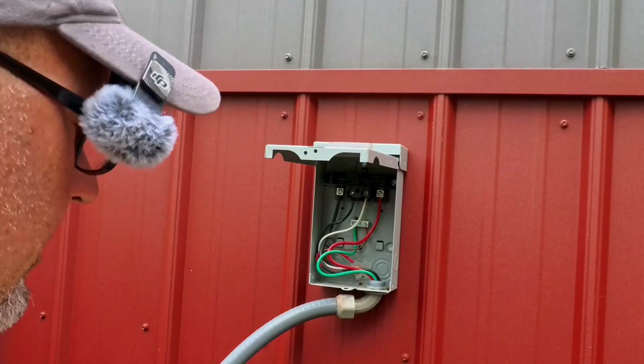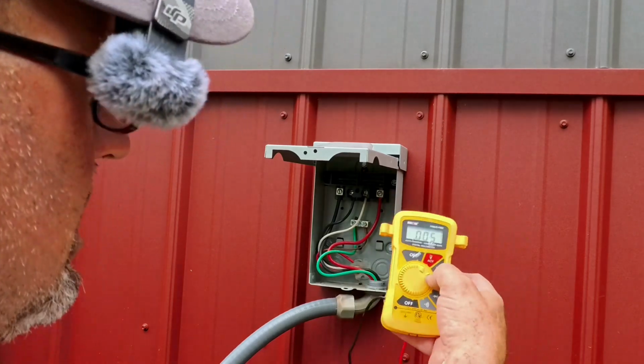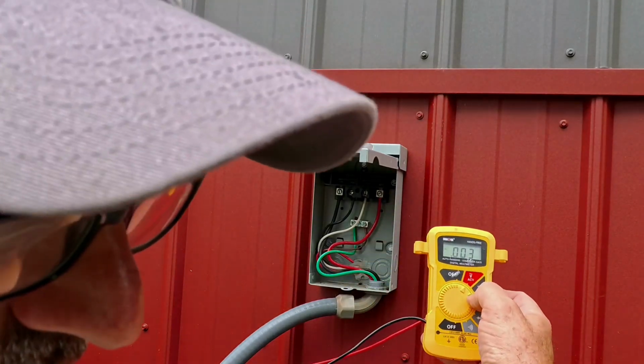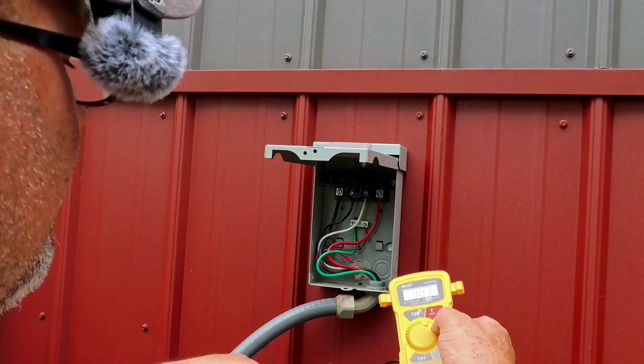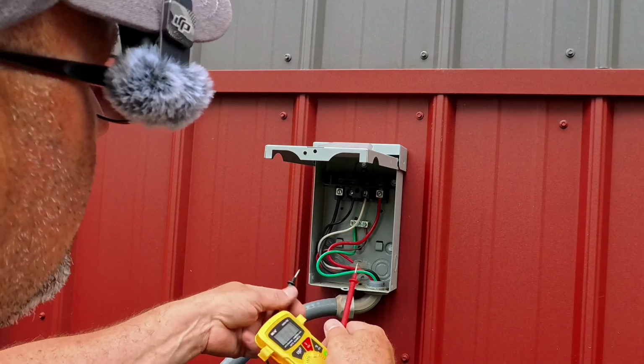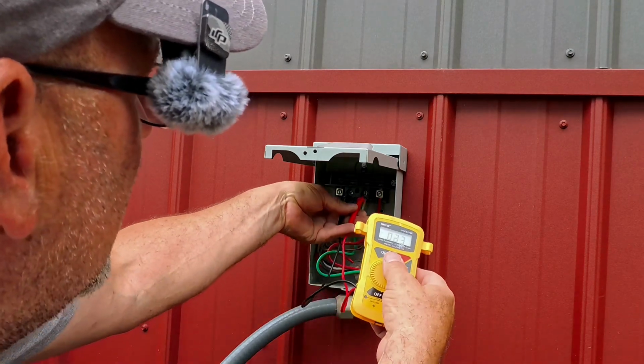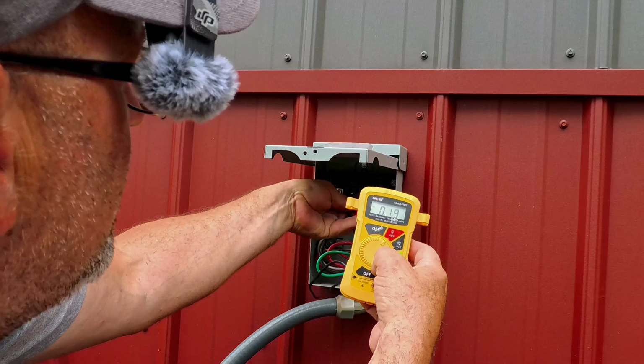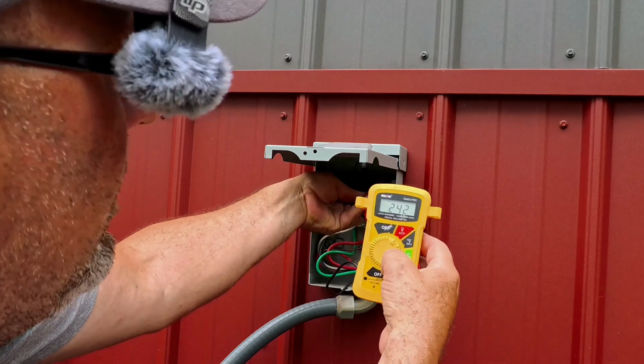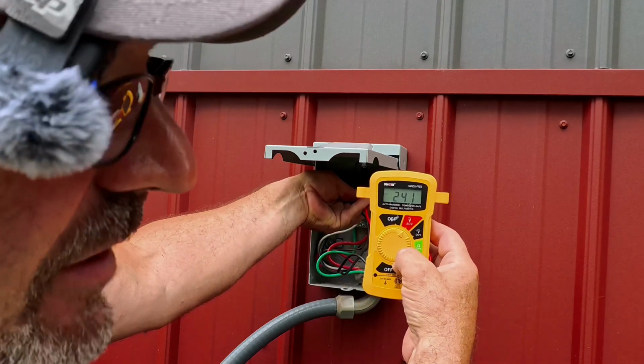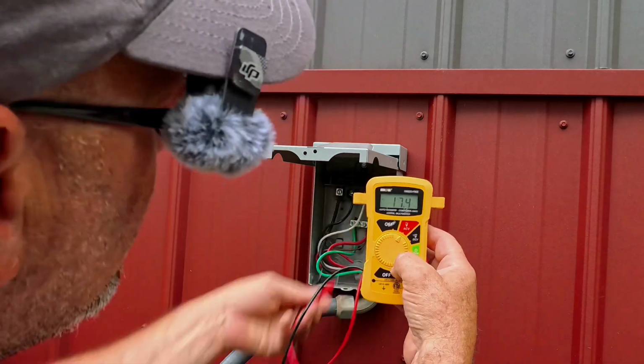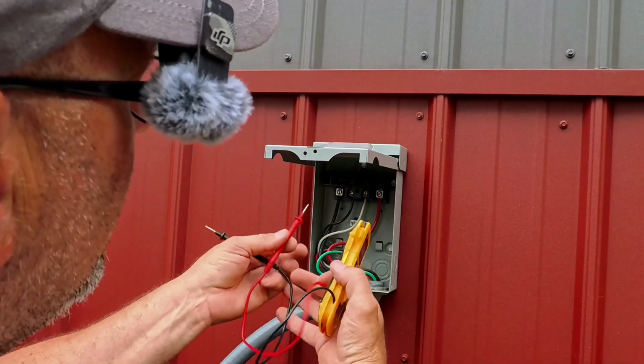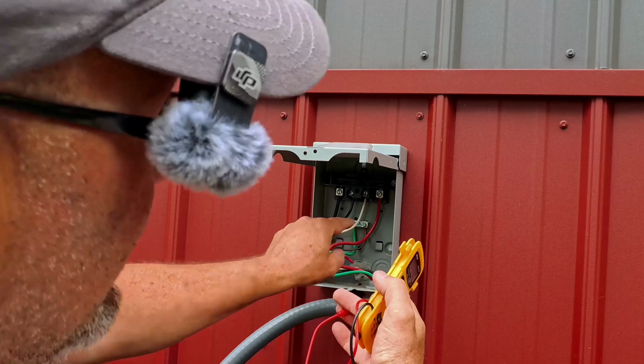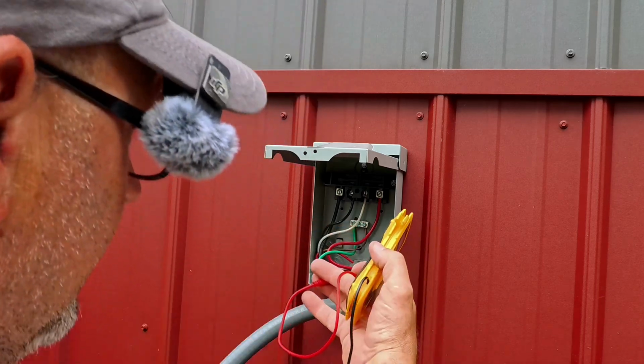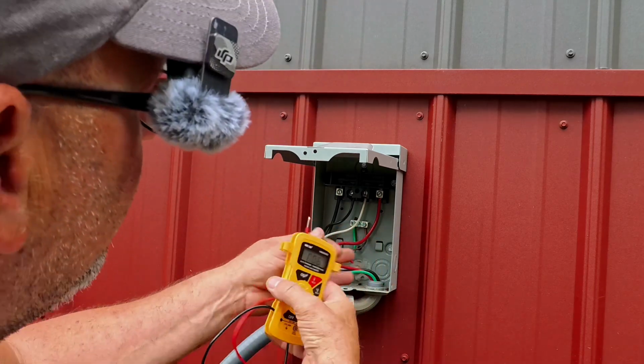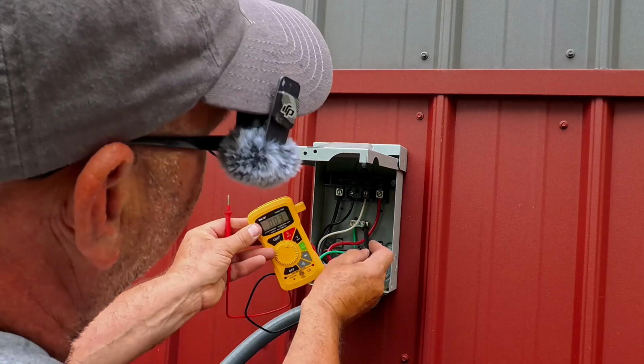So again, using our handy dandy Walmart special voltmeter here, I think this was like $24 or something. It's pretty handy to have around. We're going to check our voltage to the 2 inner lines that say line on them, and we're looking for 220 to 240 volts. And we got 241 volts. Now if you had 0 there, then we would check from our ground in the center to each terminal individually, and we should have 110 volts on each line.